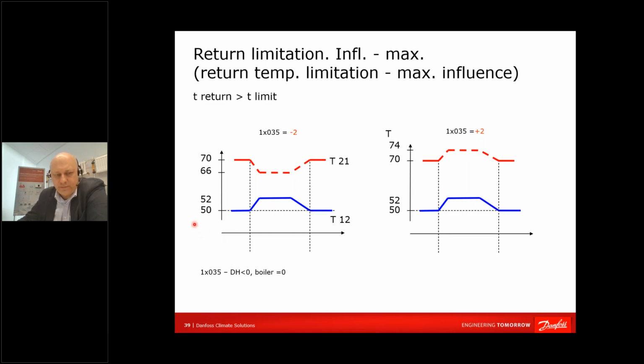For example, if you would like your return temperature to not be more than 50, what happens if you set a specific parameter to digit -2? X stands, for example, for 1, so it would be related to circuit 1. If it were 2, it would be related to circuit 2, and so on. So your return temperature went up by 2 degrees. Your setting is -2. So you are reducing the supply temperature by a correction of -2 times error 2. So you are reducing your supply temperature by 4 degrees. Simple. And if you put +2, then you will get the opposite.